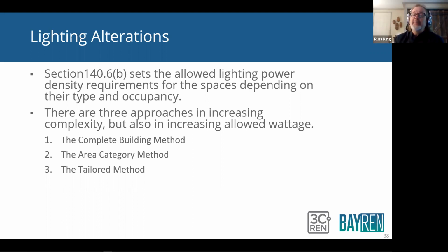There are three approaches to determining your lighting power density. All right, and again, this is all just trying to make the energy code more flexible. They could just say, here's your lighting power density, deal with it, but they don't. They say, here's one way to figure lighting power density. It's simple. Here's another way to determine your lighting power density. It requires a little bit more work, but you get a better number. Here's a third way to determine your lighting power density. It requires a lot more work, but you get a much better number, an easier number to meet, a more customized number for your specific occupancy, okay?